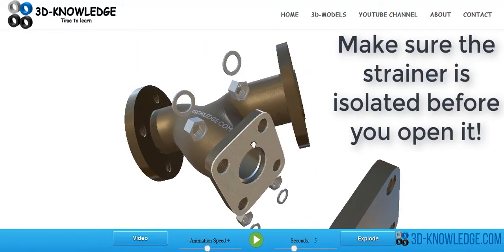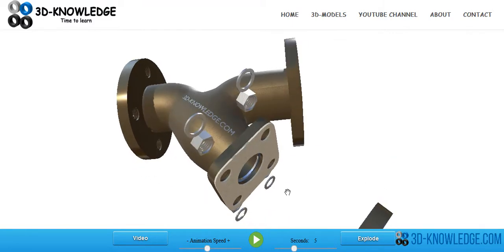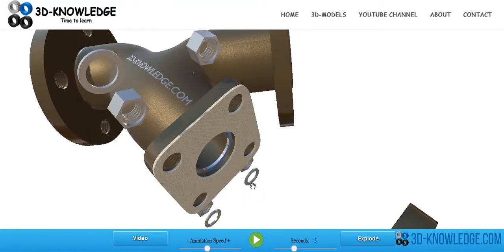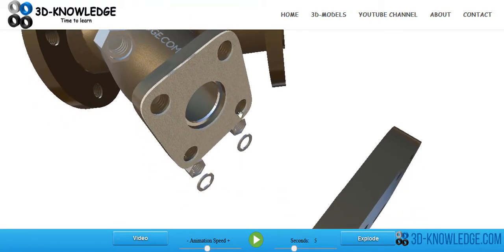Normally, for a freshwater system like this, I'm assuming this is for a freshwater system, you can expect 3 to 4 bar. But even then, 3 or 4 bar of pressure is quite a lot, especially when you're trying to get something back in, like a drain plug. Now, if you are ever working on one of these Y strainers and you have to take them apart, you should have a spare gasket to hand just in case this one here is damaged.